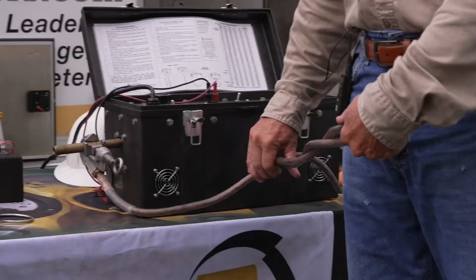You also want to make sure when you test your TPGs that you test them in a parallel configuration. The reason is to mitigate any magnetic field as much as possible, and it also mitigates any thermal activity from getting too hot, above and beyond normalcy.